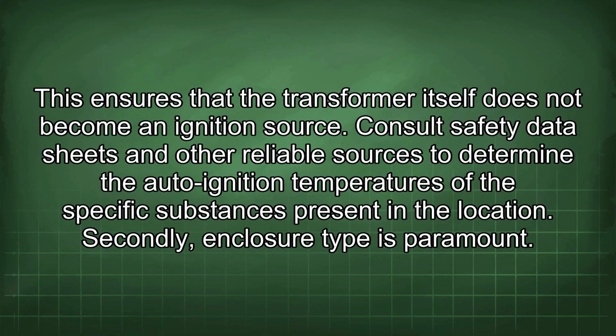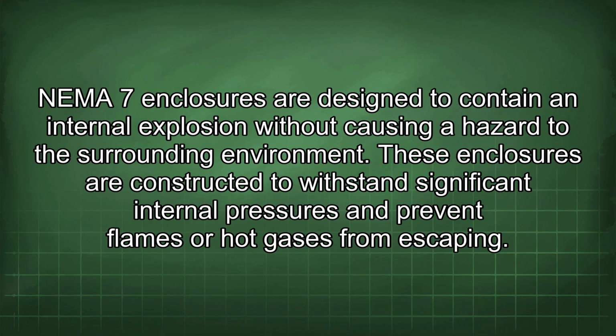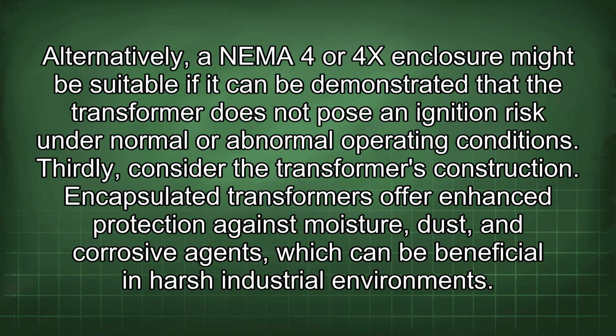Secondly, enclosure type is paramount. NEMA 7 enclosures are designed to contain an internal explosion without causing a hazard to the surrounding environment. These enclosures are constructed to withstand significant internal pressures and prevent flames or hot gases from escaping. Alternatively, a NEMA 4 or 4X enclosure might be suitable if it can be demonstrated that the transformer does not pose an ignition risk under normal or abnormal operating conditions.